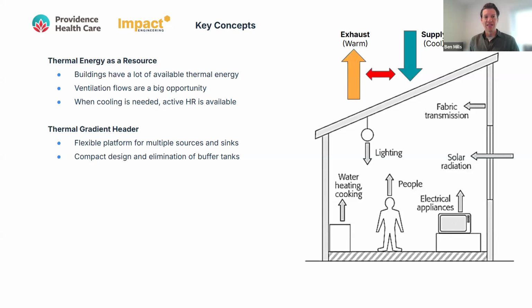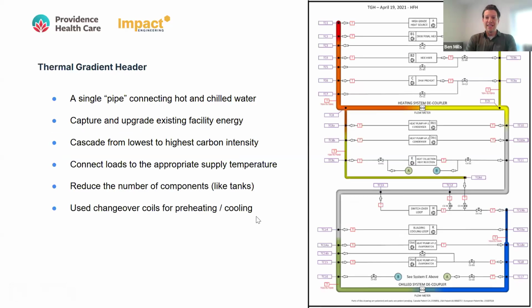It's also very compact, which is another really big feature of it, which you'll get from the next slide here. It looks complex on the right, but that's just because it's showing all the valve connections and so on. But if you focus on the color coding, one of the major innovations is that it's a single pipe, and it connects everything from your hottest heating source, like a traditional boiler making really hot water at the top in red, and your chillers making really cold chilled water in blue at the bottom.